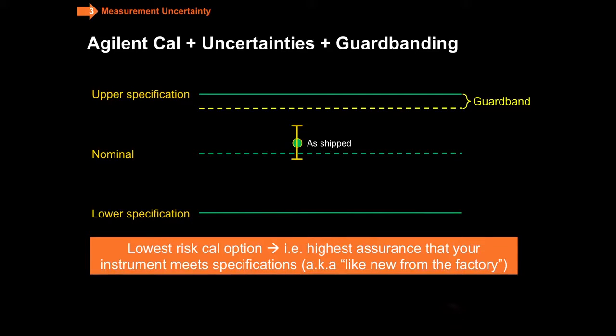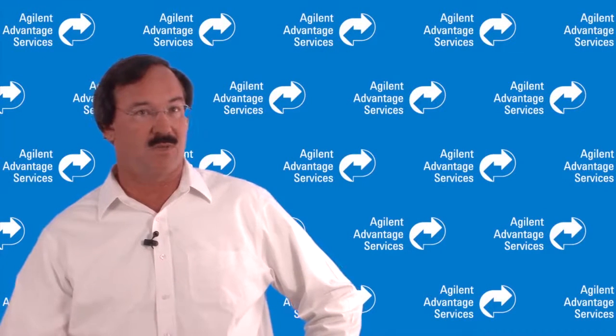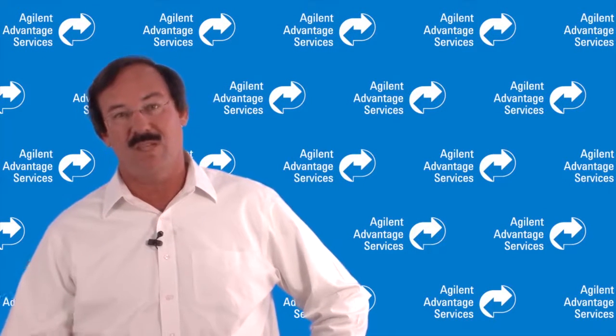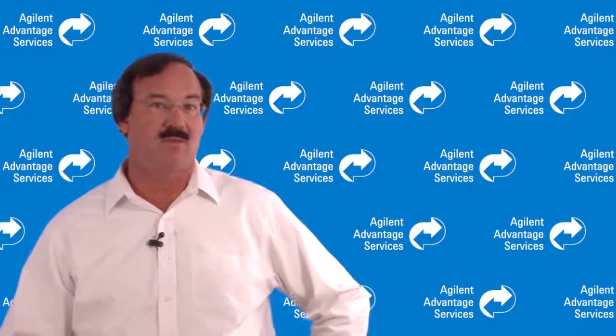So this represents the lowest risk calibration. Risk in terms of the result that's reported may be incorrect. If you need the highest assurance that your instrument meets the specification, for example, like new from the factory, then this is the calibration service that would be best for you. We provide choices because not everyone needs this, but for those who do, this is why we have it. Now you can understand what it is and if it's right for you.